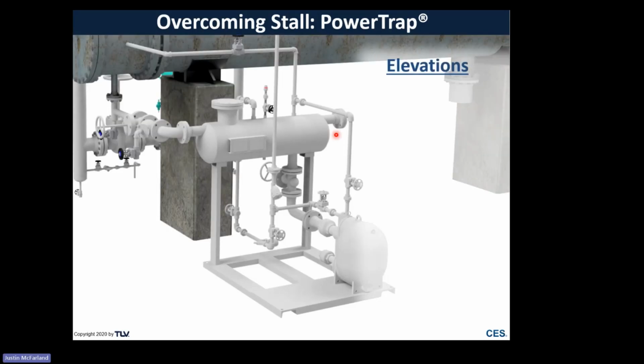So a few important points here. Elevations. So we've got our reservoir elevation. We've talked about hydraulic head. This is a way to help increase the nominal pump capacity. So if we're able to increase this elevation, we're effectively allowing more condensate to build up upstream of the check valve. And because this check valve has a cracking pressure, it's going to limit the amount of flow. So if we can increase the head pressure upstream of the check valve, that will allow more condensate to flow through that check valve.